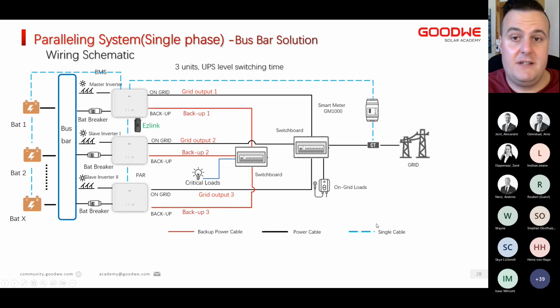Then the next solution, which is the busbar solution. This will work with some batteries already, most likely BYD, Pylontech, and those kinds of batteries that can already have one big parallel battery bank. That you should be able to do as well, where you have all your batteries connected to a busbar, and then connect the batteries to the inverters and the backups all together as well. So for me personally, this is a much nicer solution.